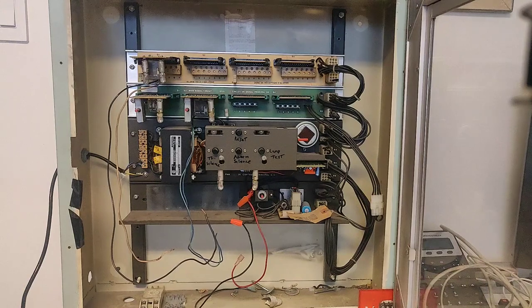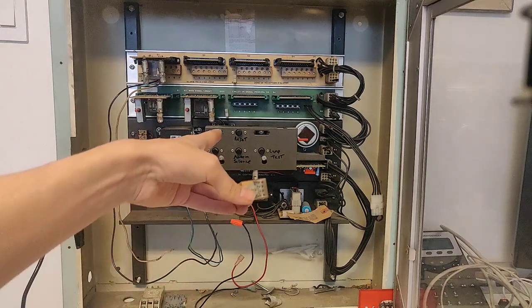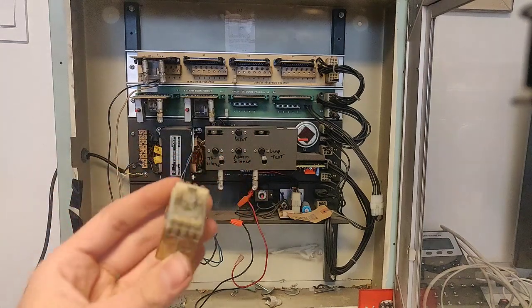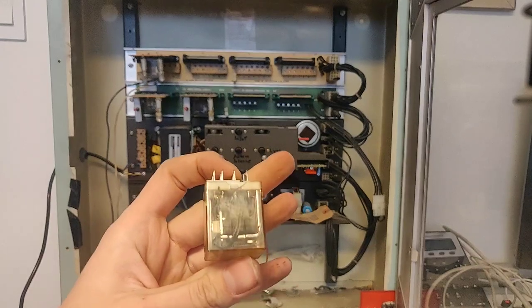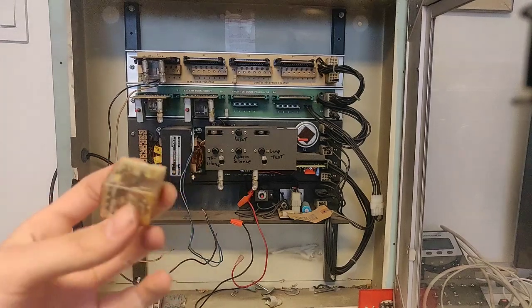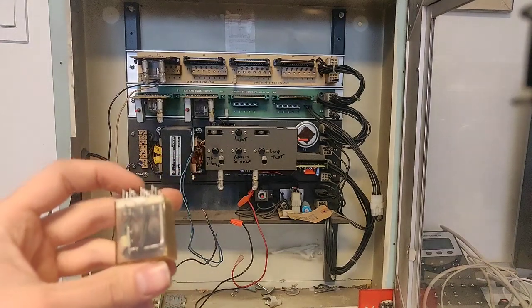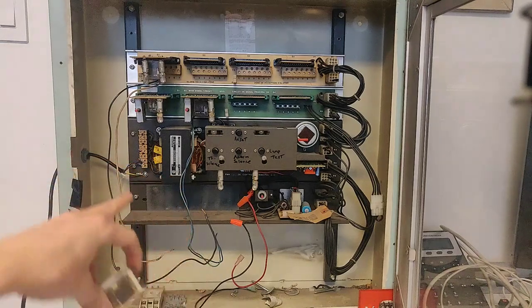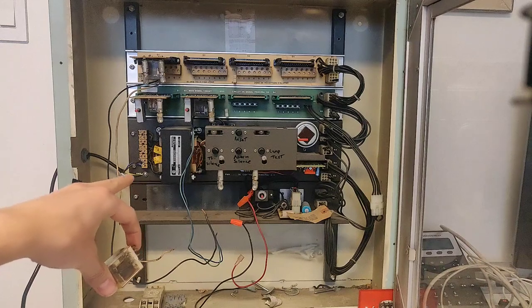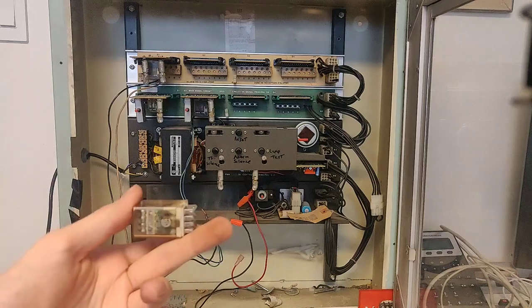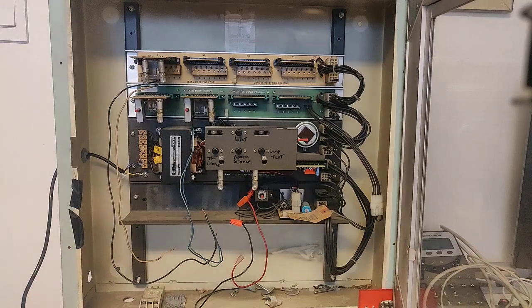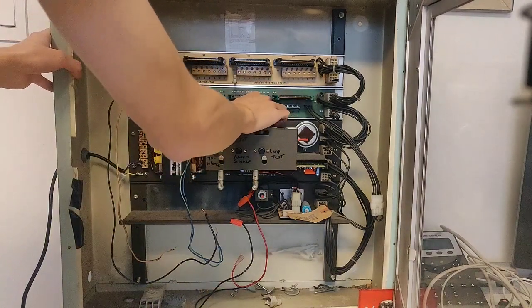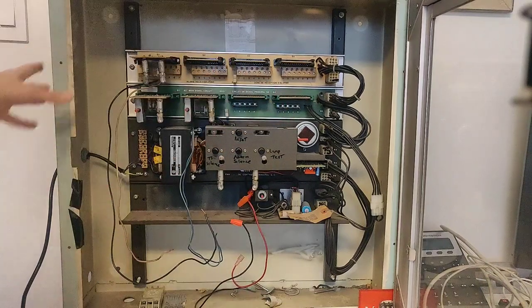This is one of the most critical failure components: this relay. This is the alarm relay that belongs right up in there above where the reset button is in the back. This relay—look at it, it's crispy. These always look crispy in these panels, and I think a lot of these panels get thrown away because this relay goes all messed up. So for fire alarm collectors or people that don't care about it being UL listed or original, you can sub this out for a 30 volt relay. This transformer often cranks out more like 28 volts or so, and it just burns this relay up. So I would suggest throwing in a 30 volt relay, but I'm going to keep this one for the time being because it's what I have on hand.